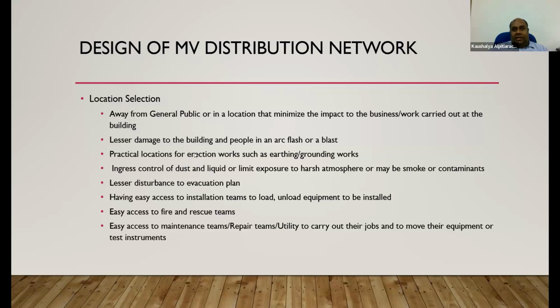And ingress control of dust, maybe liquid, or limit exposure to harsh atmosphere, or maybe smoke or contaminants generated by the application itself or neighboring applications. Liquids, in the sense, maybe flooding. The flood levels have to be considered, and your location shall be selected with an idea of the last flood level, keeping an extra safety margin. You may have to decide what altitude you are going to place your switchgear and medium voltage equipment and loads, not only medium voltage, all the electrical equipment.